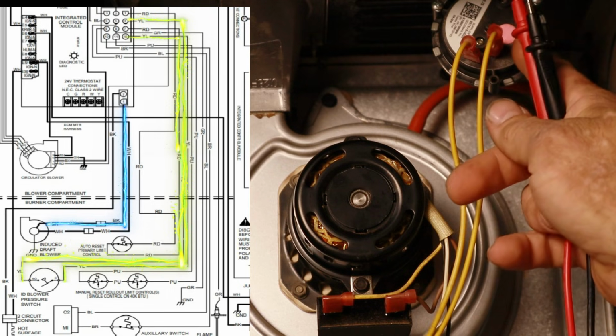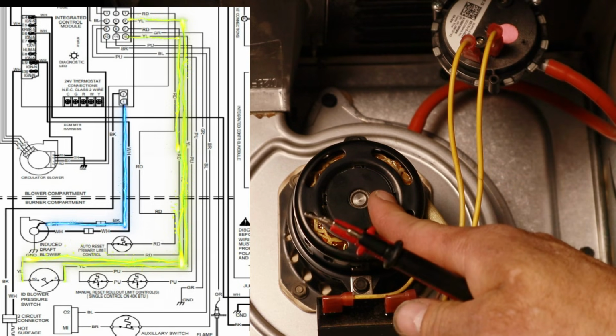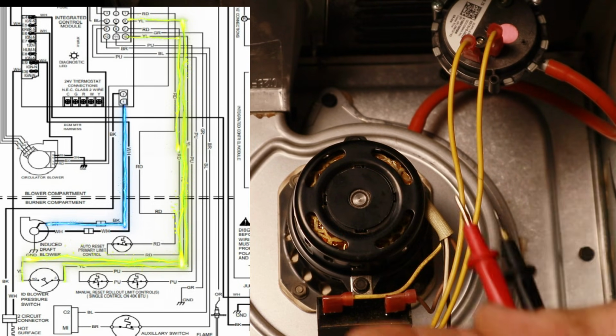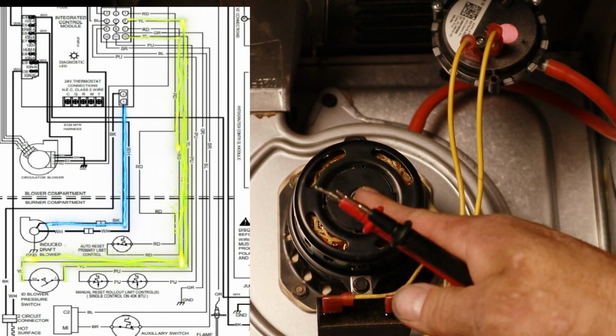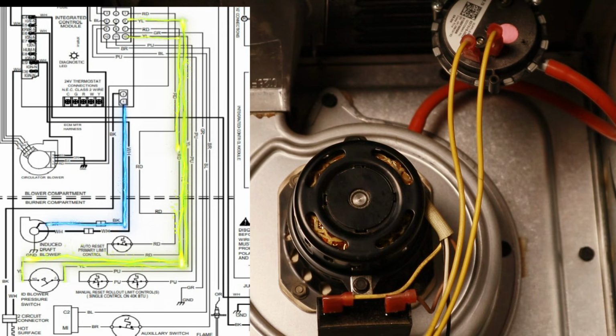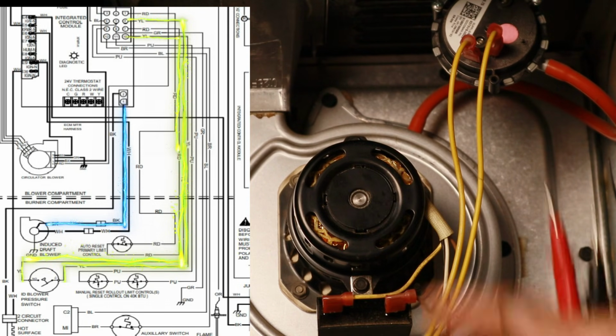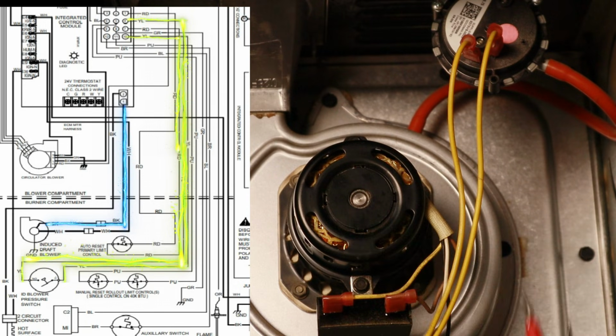So basically this pressure switch just proves that this motor is running, because we don't want to fire up the unit without this running. The air is not going to be pulled into the unit without it, and our flame is going to roll out, and it's going to set off our flame rollout switches, and everything's going to shut down.